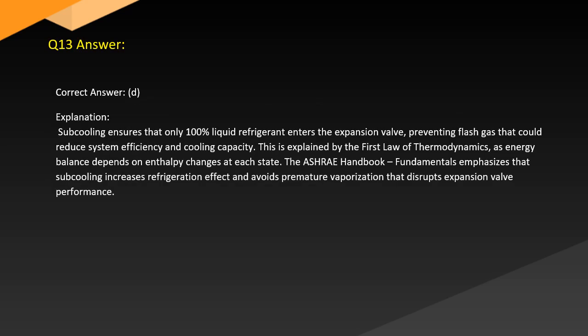Answer. Correct answer: D. Explanation. Subcooling ensures that only 100% liquid refrigerant enters the expansion valve, preventing flash gas that could reduce system efficiency and cooling capacity. This is explained by the first law of thermodynamics, as energy balance depends on enthalpy changes at each state. The ASHRAE Handbook Fundamentals emphasizes that subcooling increases refrigeration effect and avoids premature vaporization that affects expansion valve performance.